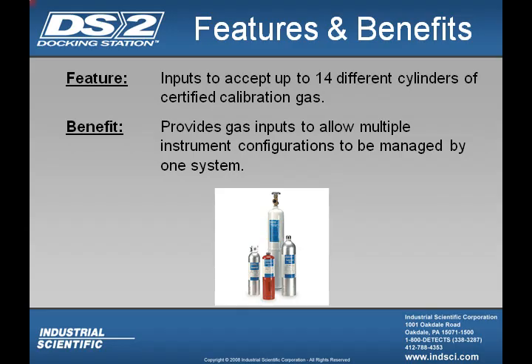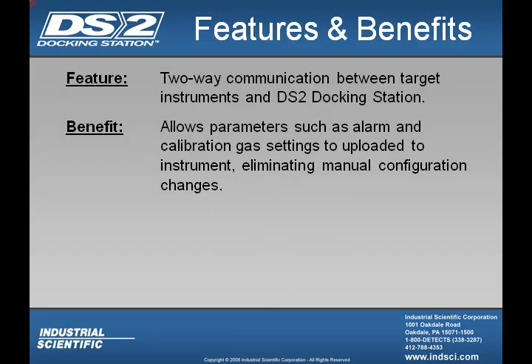And on the back of your docking station, it can accept up to 3 different calibration gases, and these inputs can accept up to 14 different types of calibration gas. And this provides gas inputs to allow multiple instrument configurations to be managed by one system. You also have 2-way communication between the target instrument and the DS2 docking station, and this allows parameters such as alarms and calibration gas settings to upload to the instrument, eliminating manual configuration changes.